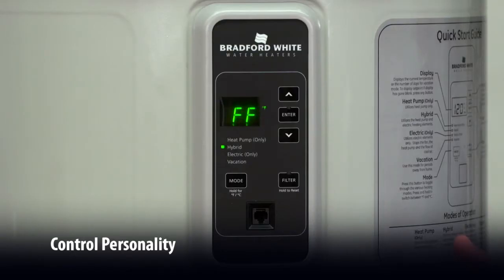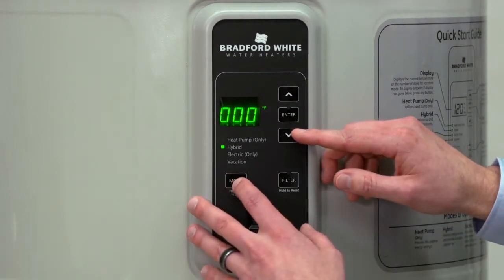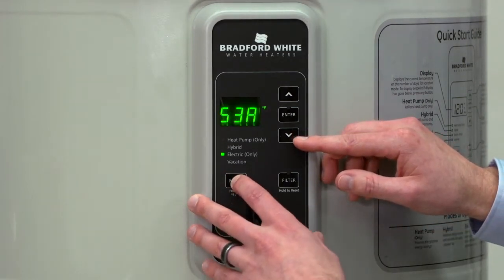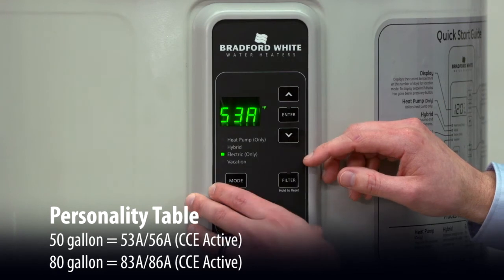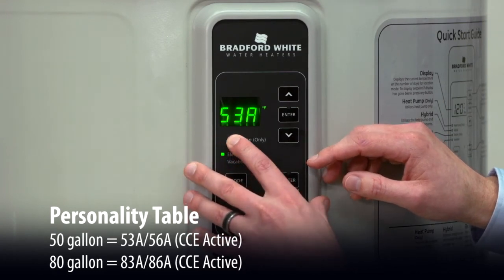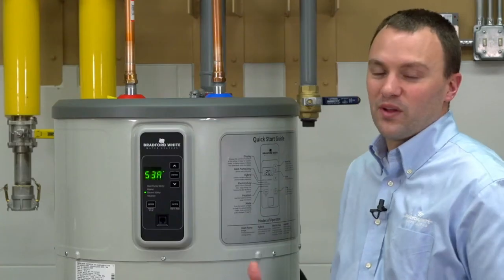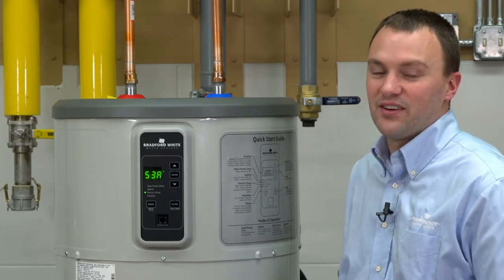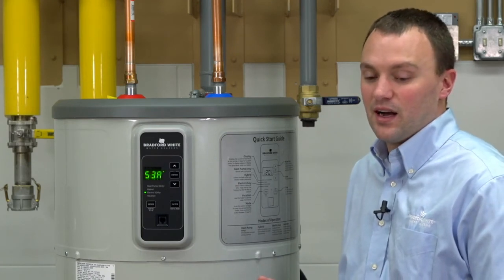Every control has a personality. We're already in the service mode, so the next step is going to be that we can check and verify our personality. So we're going to just use the mode button, and that's going to take us to our personality. So we'll see this personality is 53A. So what that tells me is this is a 50-gallon heat pump water heater.